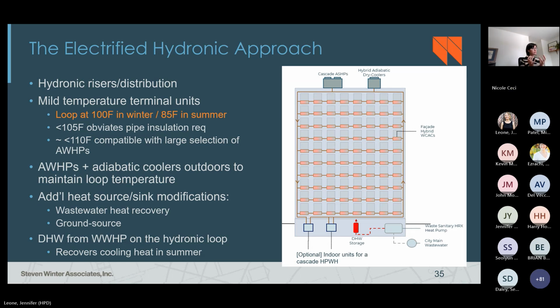So that's our distribution within the building, terminal units, and then we're feeding that loop with air-to-water heat pumps to inject heat into the hydronic loop and adiabatic coolers to reject heat from the loop. So air-to-water heat pumps to inject heat, adiabatic coolers to reject heat to maintain our target loop temperatures. A lot of air-to-water heat pumps can also reject heat. It's just the adiabatic coolers tend to do that much more efficiently. And then we also have a lot of other options for replacements or supplements to those central plant components. So for example, wastewater heat recovery and ground source fields, those are probably two of the more mature options.